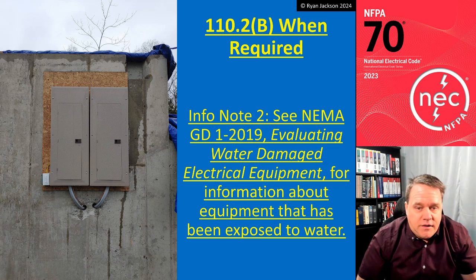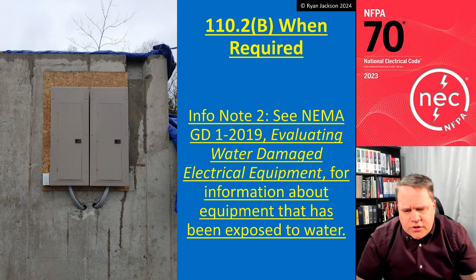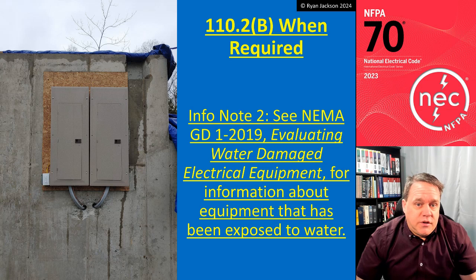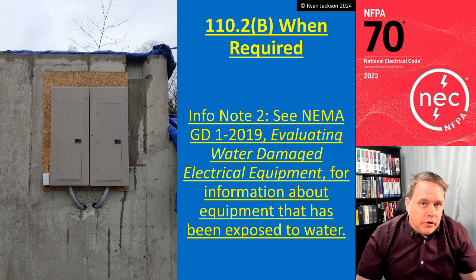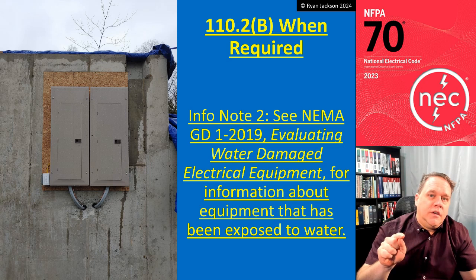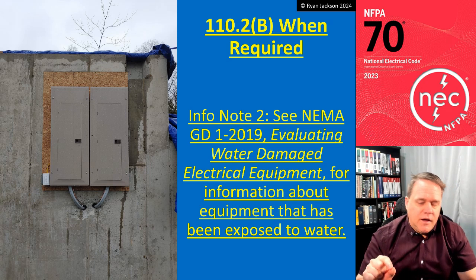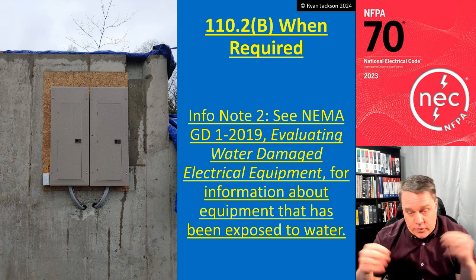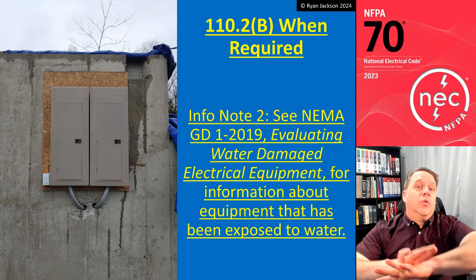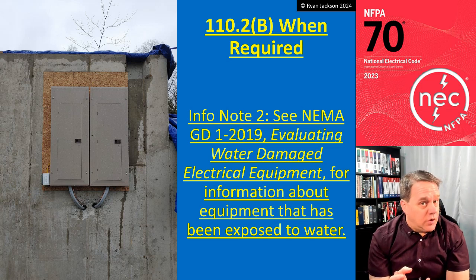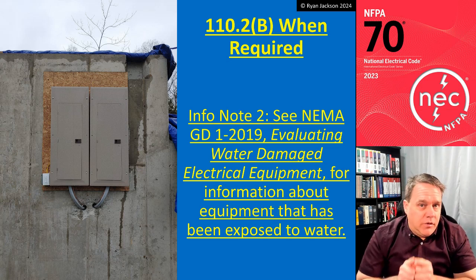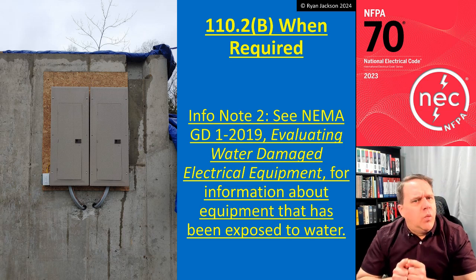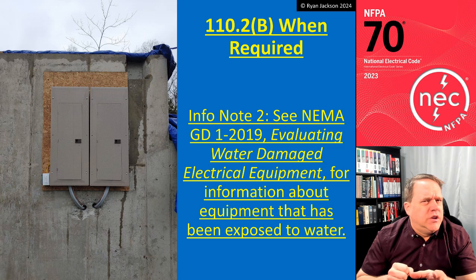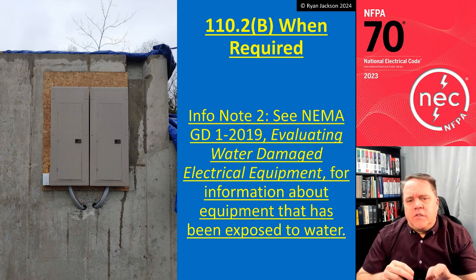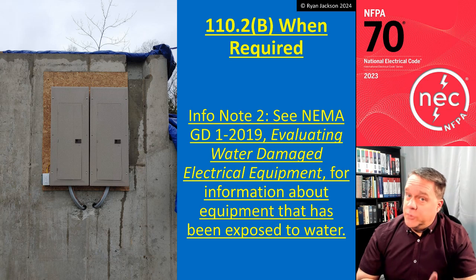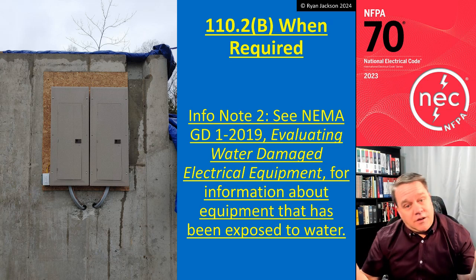Is this a code violation right here? Well, installing indoor rated equipment outdoors is obviously not allowed. However, if you're doing this during the course of construction, right? If you're installing this equipment that's for the permanent installation and you're doing it while the building is under construction, that is okay, as long as you protect it from the weather. And that's something found in, I think, 110.12(B), or maybe it's 110.13 in the National Electrical Code. So is this okay? Yes, if it's protected. If it's not protected, well, then we got a problem.